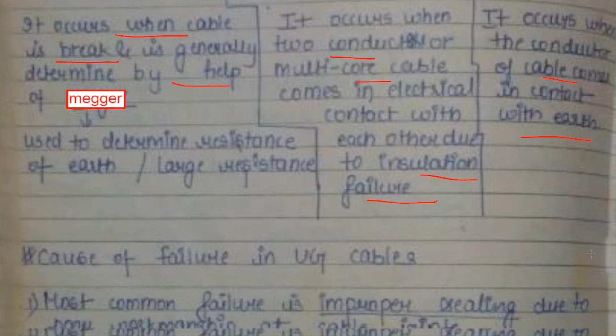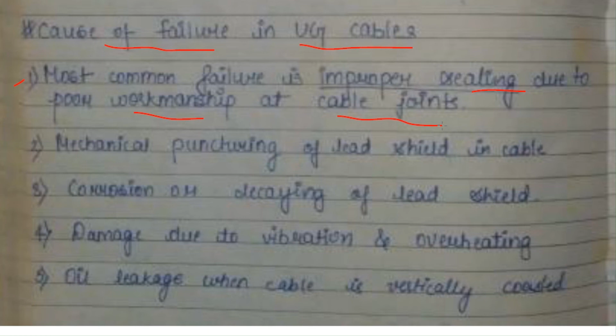Now let us discuss what are the causes of failure in underground cables. The most common failure is improper sealing due to the poor workmanship at cable joints. When the long cable is used and the two cables are joined, then if the workman or the person who is installing that creates improper sealing, then there might be a possibility of failure in underground cables. Thus, such type of cable installment requires highly skilled workmen.